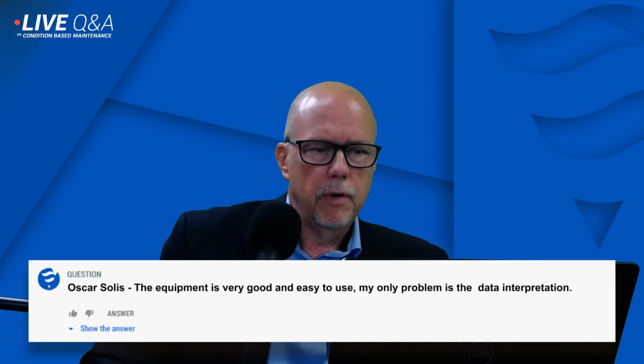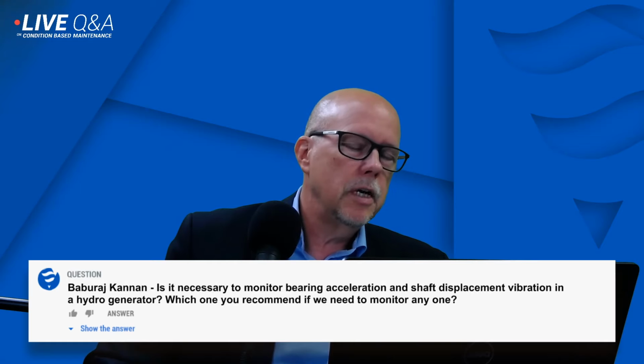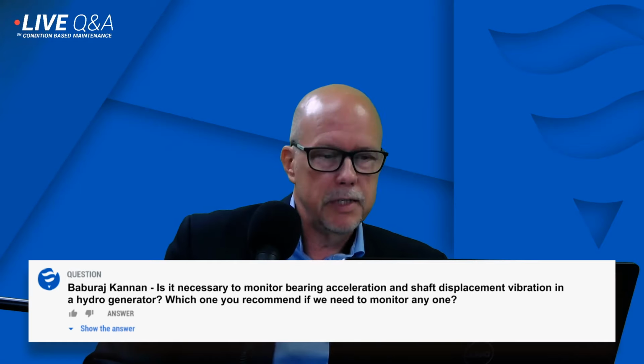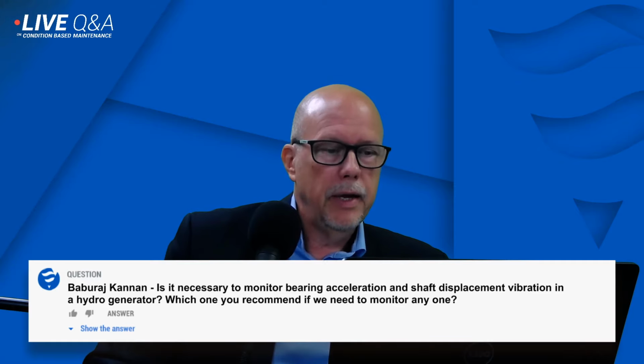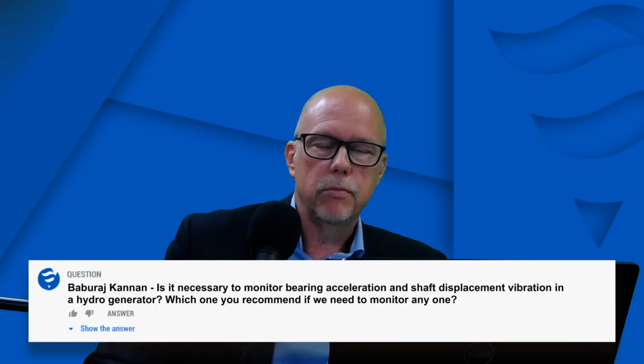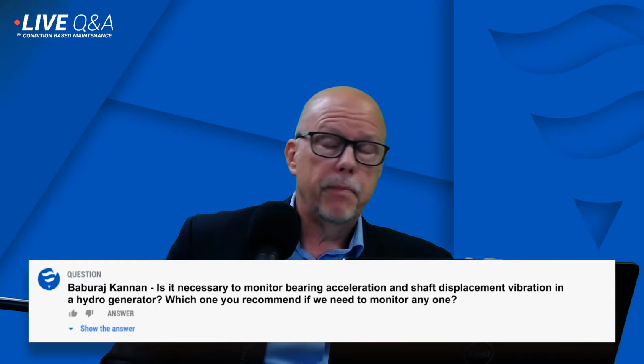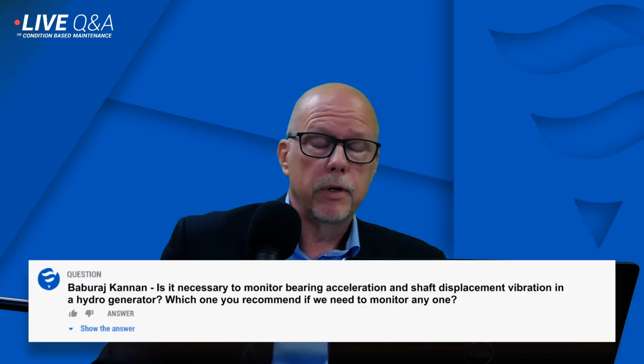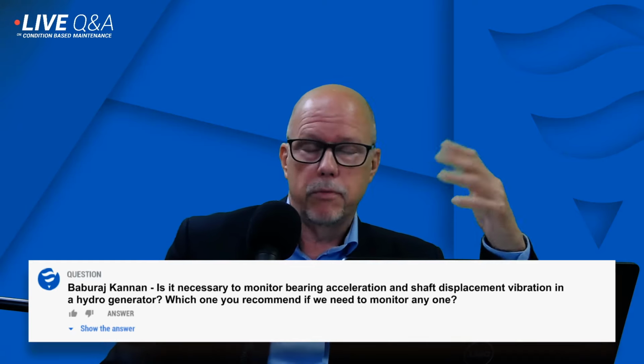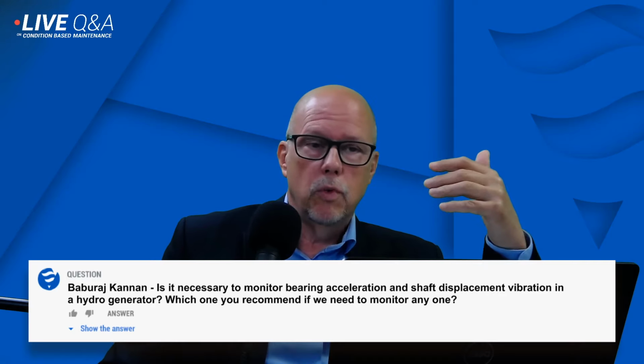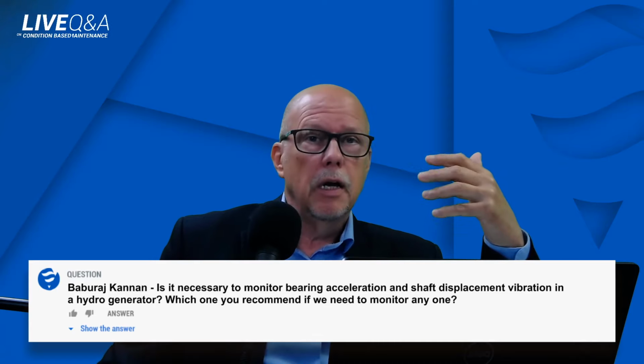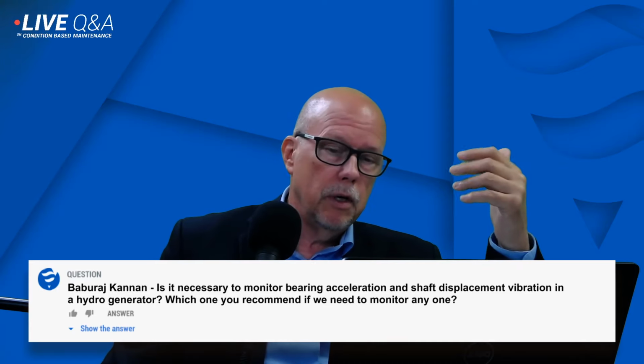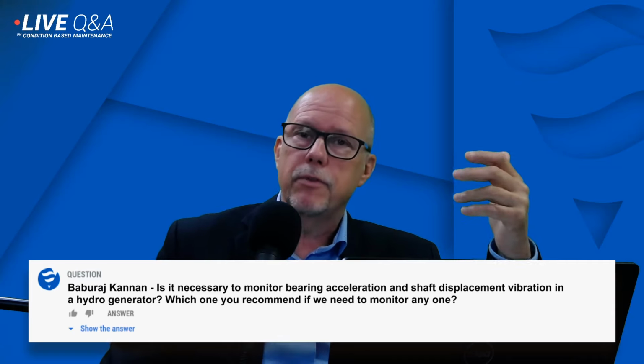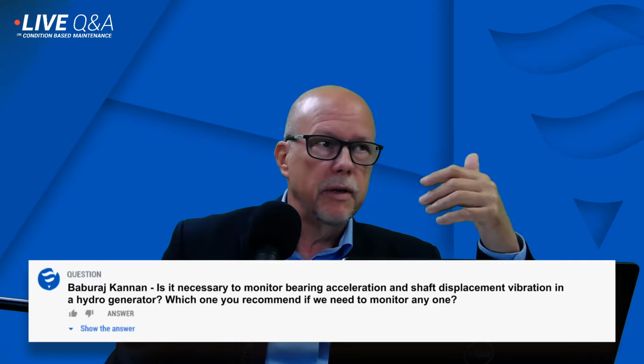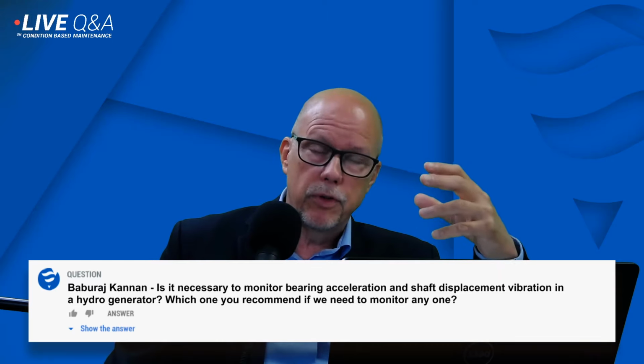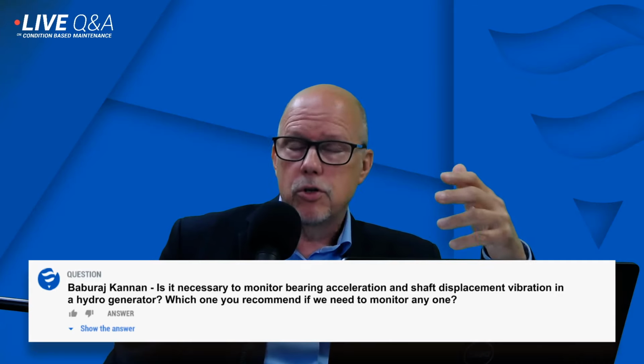We had a second question from a Mr. Kanan, who asked: is it necessary to monitor bearing acceleration and shaft displacement vibration in a hydro generator? And which one do you recommend if we need to monitor only one of them? Well, in my opinion, they're both important, but the most important one would be shaft displacement, for multiple reasons. First of all, if you want to alarm on the shaft displacement severity, you need shaft displacement probes. If you want to balance the rotor, you need shaft displacement probes to do that. So for any kind of analysis using amplitude, frequency, and phase for the shaft, the better choice is displacement.